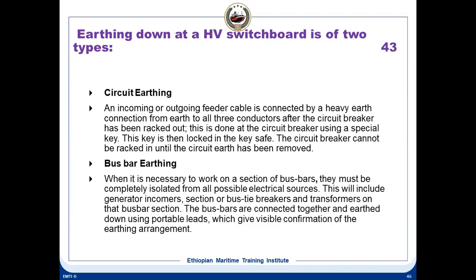Generator to the incoming of the breaker is grounded, and outgoing to the switchboard is still not grounded, because you cannot ground the switchboard. Otherwise, you will be grounding the whole switchboard. So only a grounding from generator to breaker. That is using a special earthing that is known as the circuit earthing.